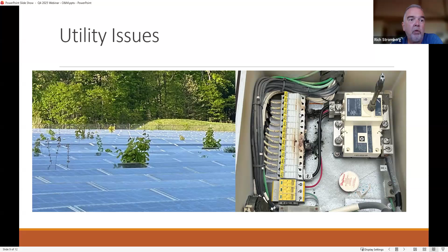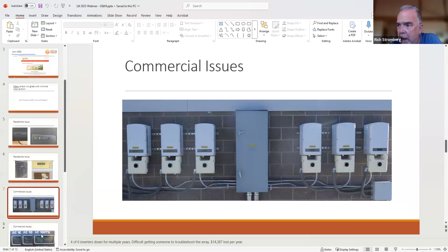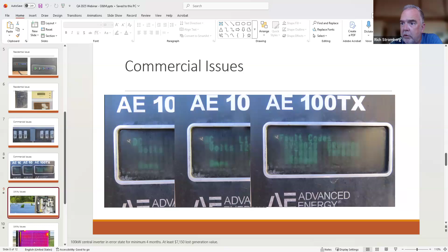Besides vegetation management, no one had been doing periodic torque checks on the cable terminations, and you can see multiple arcing spots. We found several DC combiners with issues. This system lost at least $7 grand in generation value. On this other one, annual revenue loss was at least 26,000 — one of the two central inverters was down, plus vegetation management and cable termination issues on multiple DC combiners.